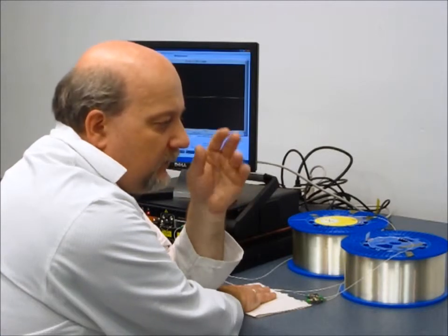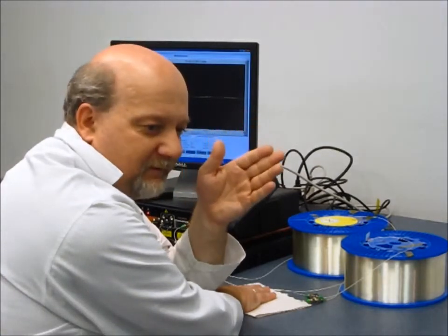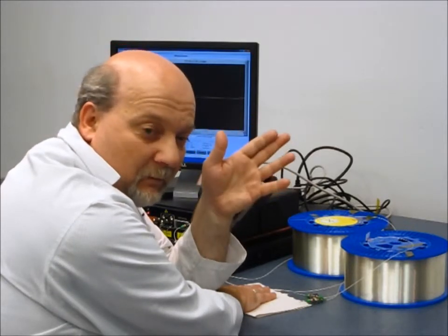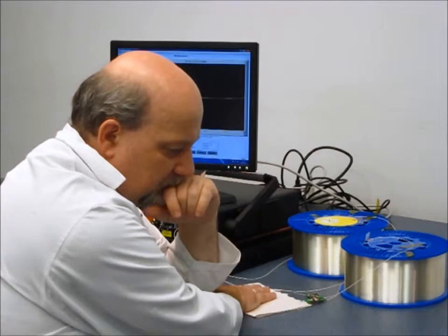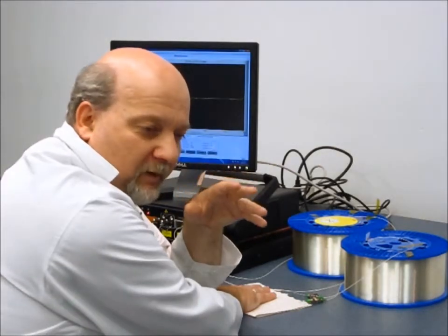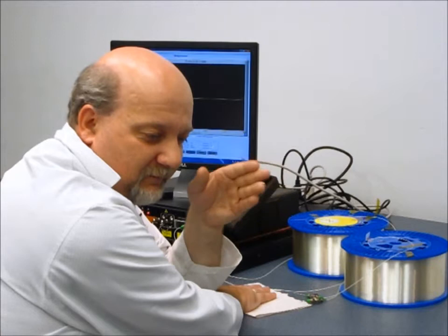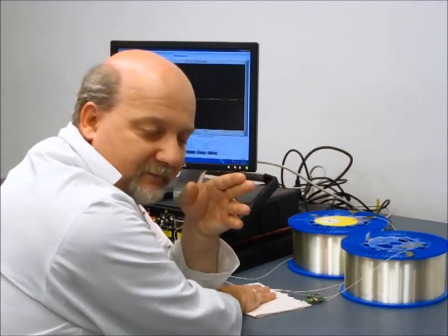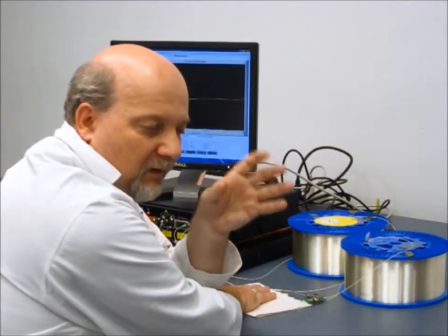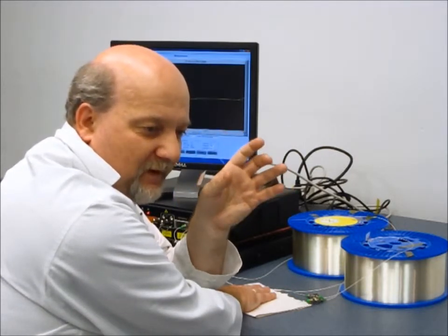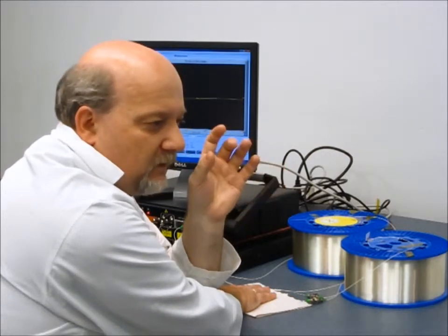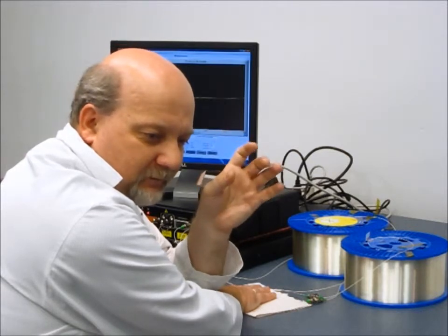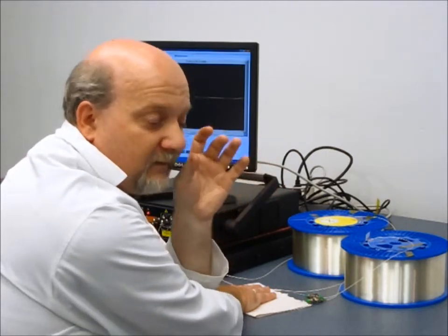Okay? Now, the fiber is going to see basically an average between my hand temperature and the temperature below the paper, so we may see something smaller as a result of this test. Also, I want to point out that this is a 2.5-meter section of fiber, and we're working with 25 nanosecond pulses, which is equivalent to a 2.5-meter section of the fiber. Okay? So we're really up to the resolution limit of the instrument here in terms of detecting this change in the temperature.